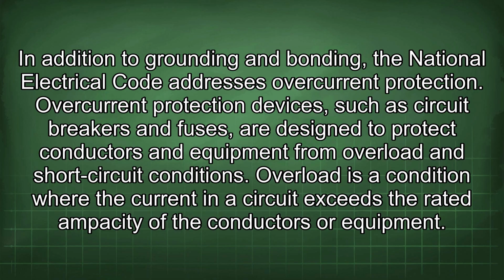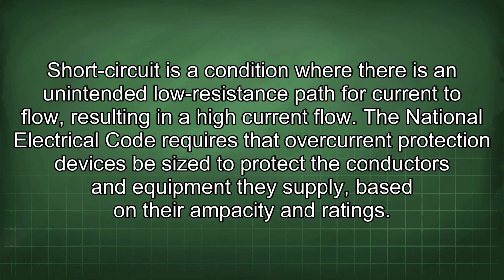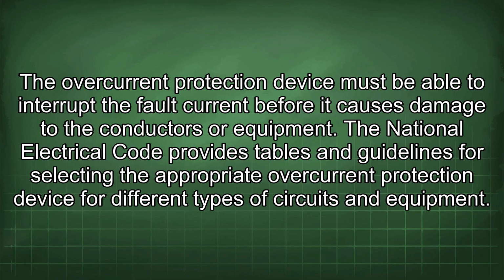In addition to grounding and bonding, the National Electrical Code addresses overcurrent protection. Overcurrent protection devices, such as circuit breakers and fuses, are designed to protect conductors and equipment from overload and short-circuit conditions. Overload is a condition where the current in a circuit exceeds the rated ampacity of the conductors or equipment. Short circuit is a condition where there is an unintended low resistance path for current to flow, resulting in a high current flow. The National Electrical Code requires that overcurrent protection devices be sized to protect the conductors and equipment they supply, based on their ampacity and ratings. The overcurrent protection device must be able to interrupt the fault current before it causes damage to the conductors or equipment. The National Electrical Code provides tables and guidelines for selecting the appropriate overcurrent protection device for different types of circuits and equipment.